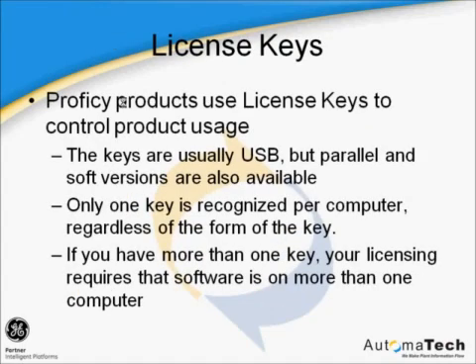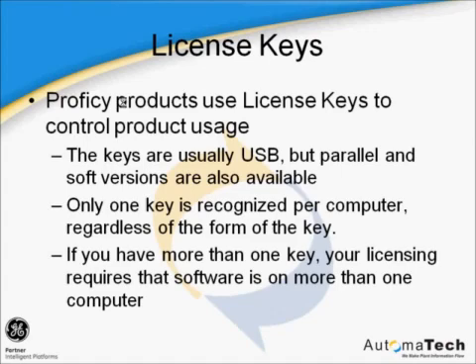The license key controls several items about the Historian. The license key is available as a USB device, a parallel device, or as a software license, which is also referred to as a keyless license. This key controls which options of Historian are available to use, the number of distinct tags that you can collect, and the number of clients that can connect to the Historian server. Note that these client connection restrictions do not apply to collectors or trending historical data in iFix and CIMPLICITY.